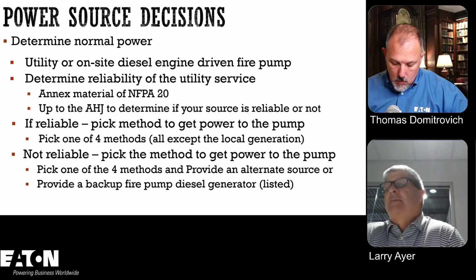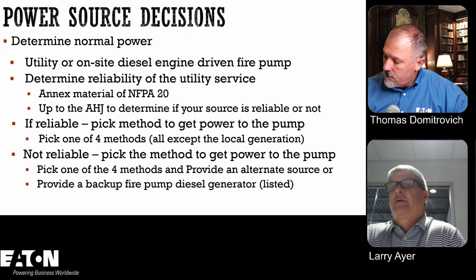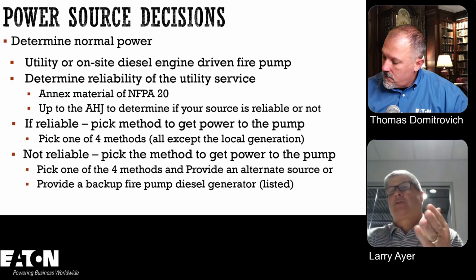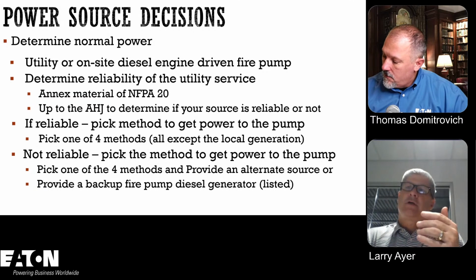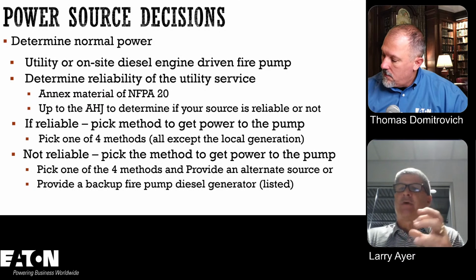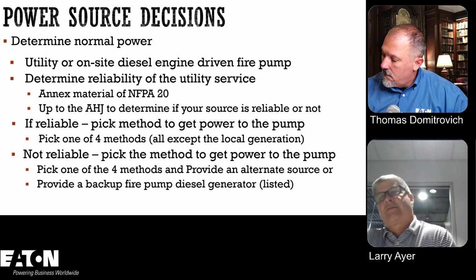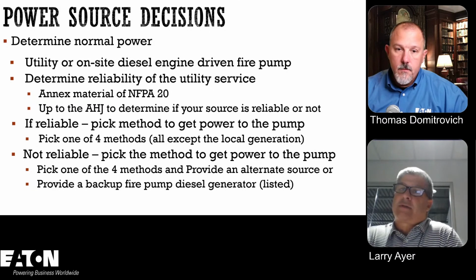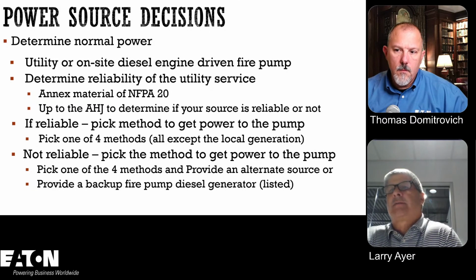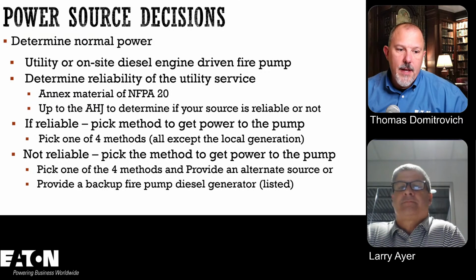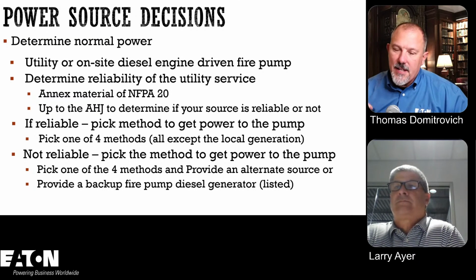So maybe the voltage, maybe you bring in 13.2 into your building and you have to step it down. And once you bring 13.2 in, now you're in a different animal, and you've got to provide transformers for the fire pump and things like that. So maybe sometimes it's a cost consideration to look at an engine-driven fire pump. Yeah. You said something important that just sparked something with me: the proximity of the service to the water supply. That would be very important, wouldn't it?